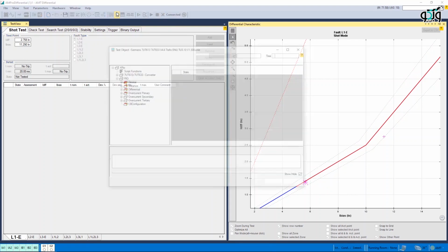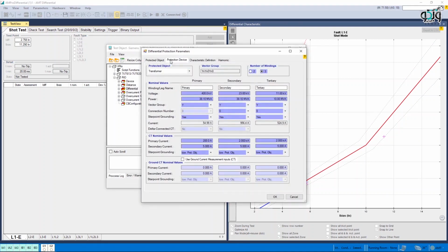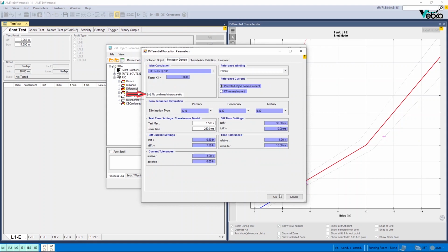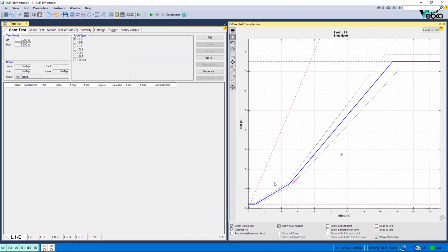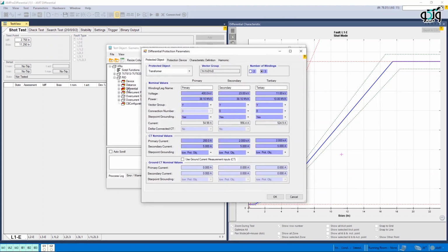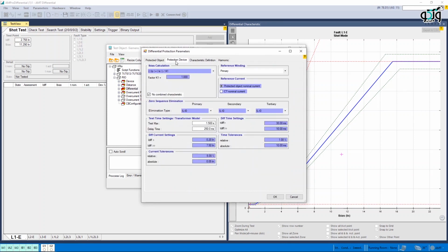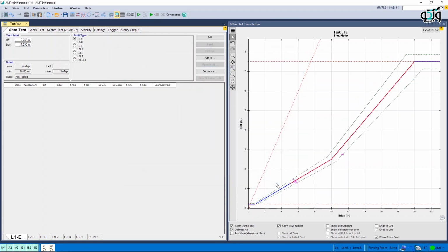This means that if you have brought a general trip to the device to test single-phase faults such as L1E and checked the No Combined Characteristic option, in some of the area close to the characteristic curve, the relay performs a trip for the L1E fault, but this trip is not the trip of the L1 phase, but it is related to the current of the two other phases, which can also be observed by using the characteristic of the delta point on the curve. If in the same condition the No Combined Characteristic option is unchecked, you can see that this point is located in the tripping zone.